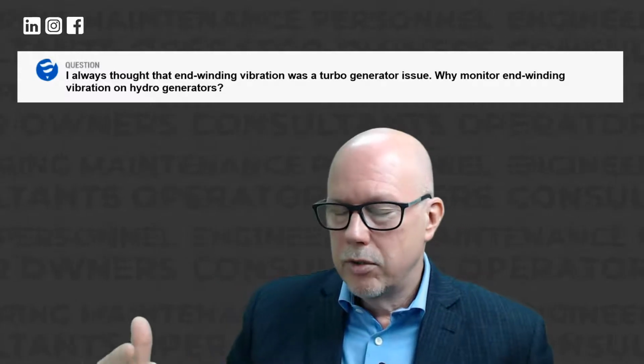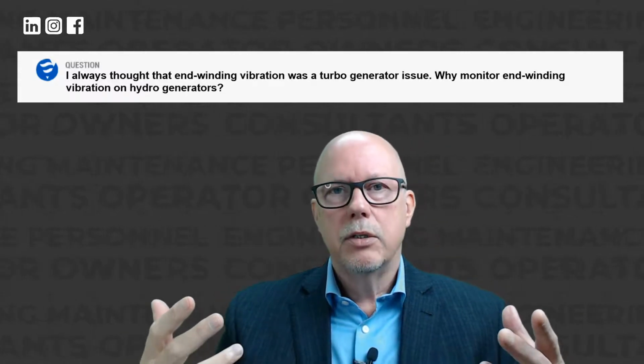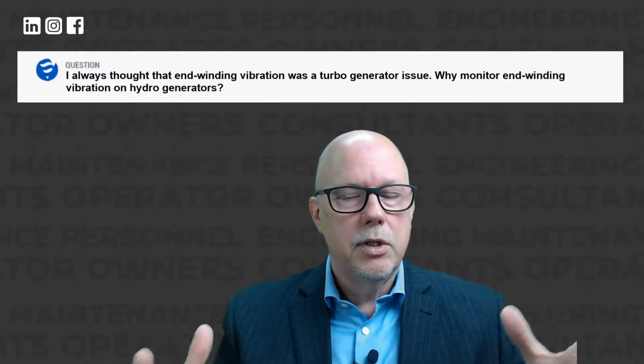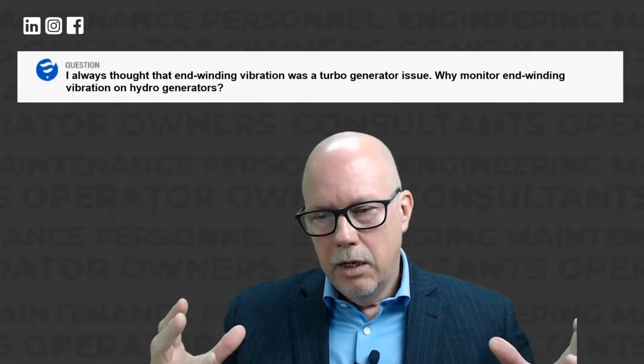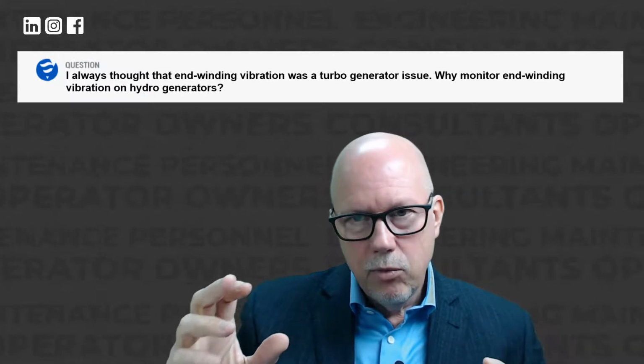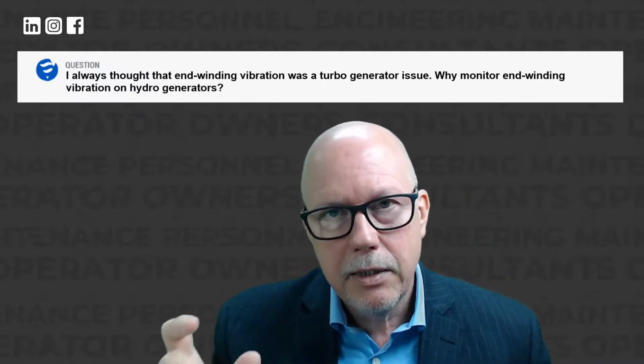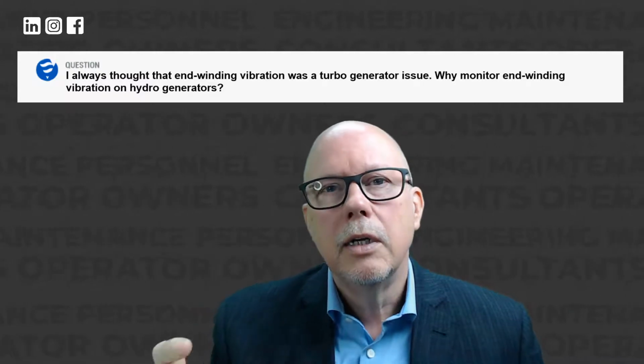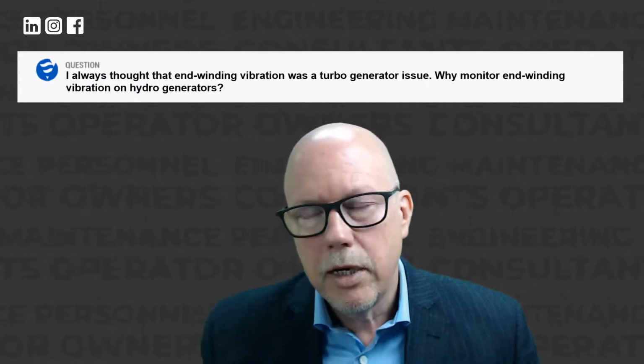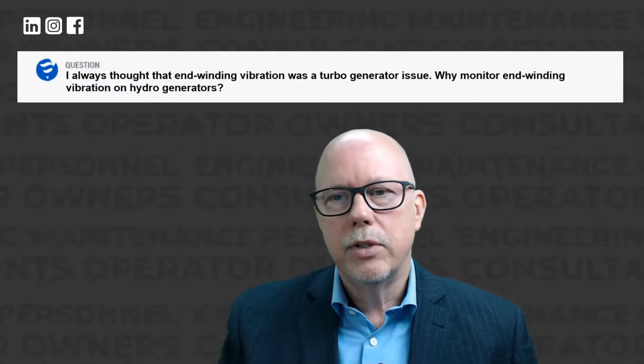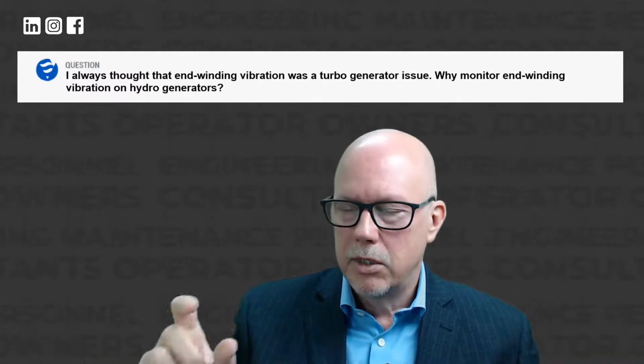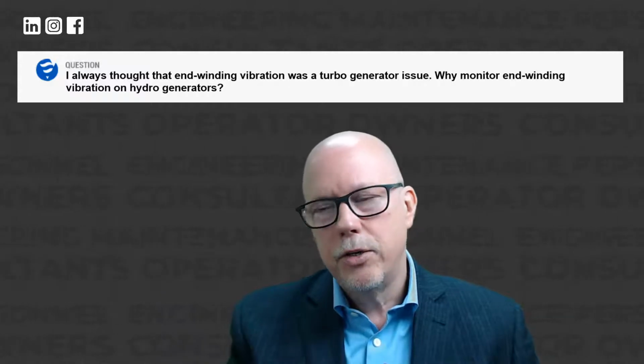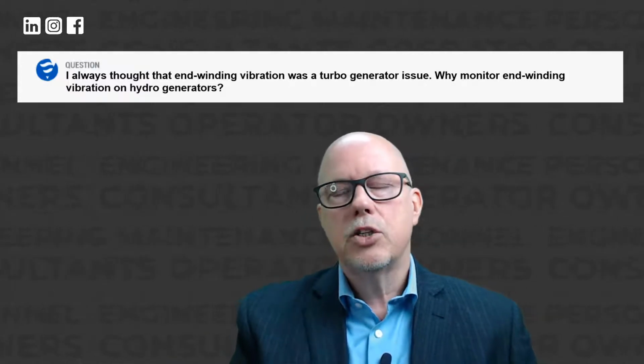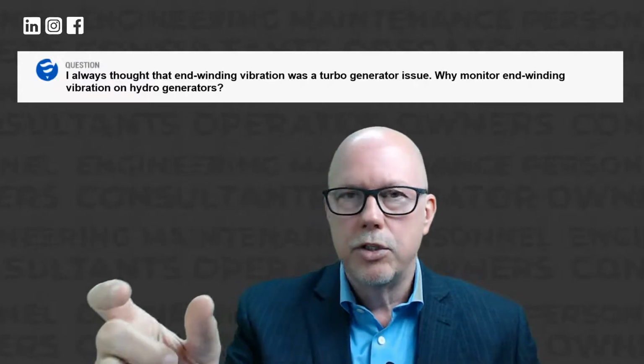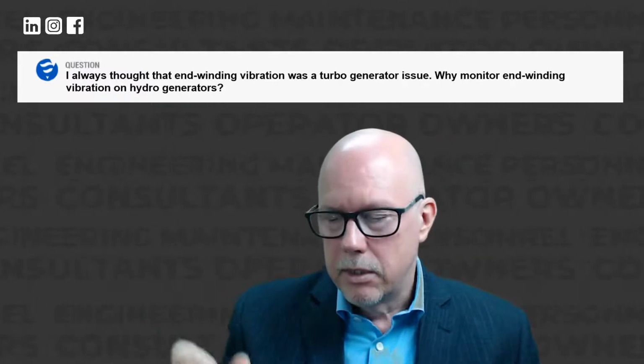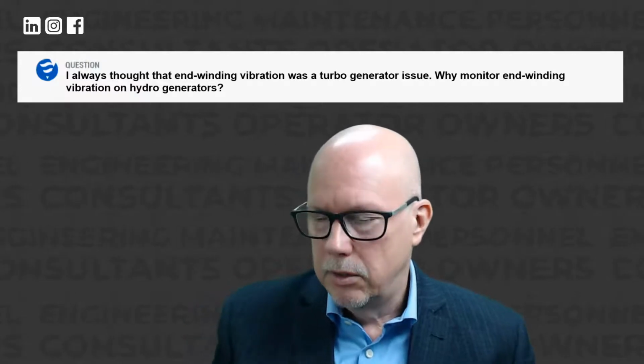So that goes to show that when you monitor end winding vibration, because of the cost involved, you're limited in the number of sensors you can put in. If you see vibration that's high in one location, you have to remember that may not be the highest level of vibration on the unit. So you can't say, well, the vibration is high, but not the end of the world, we can live with it. You should go in there and do an inspection, because it is possible that the vibration you're picking up on bar X is actually being generated by bar Y, which is adjacent to it and is vibrating tremendously. So it was an eye opener for them.